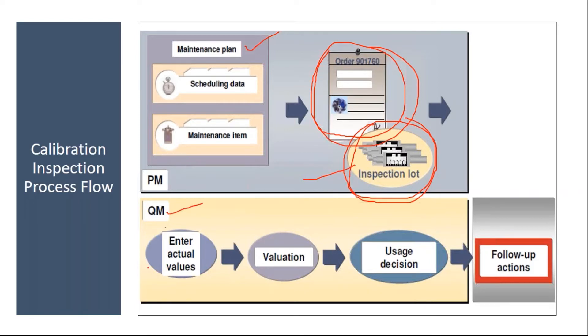Once the inspection lot gets generated, in the QM module they will do the calibration — they will enter the calibration results in the lot, do the valuation, and finally do the usage decision. In the usage decision they mention whether that equipment can be used or not, whether it is usable or has to be discontinued.